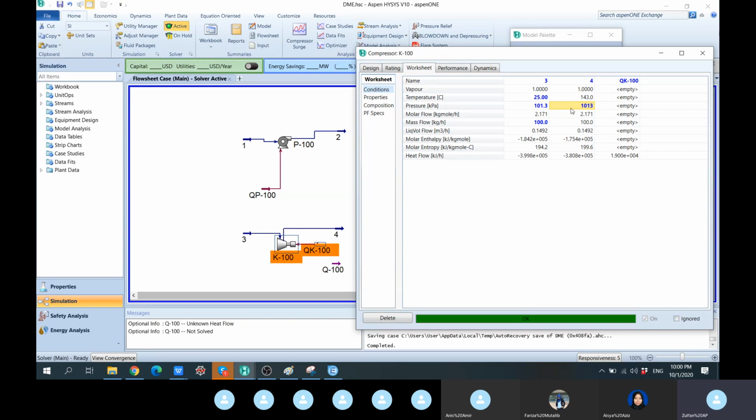But in this particular case, because we have a very special chemical, we can even stretch to 180, 10 times further. But if your temperature is not 25 degrees C, but 50 degrees C, now you are not so okay with 10 times of compression ratio. So in this case, if we start at 50 degrees C, we have to reduce it to 9 atm, for example.